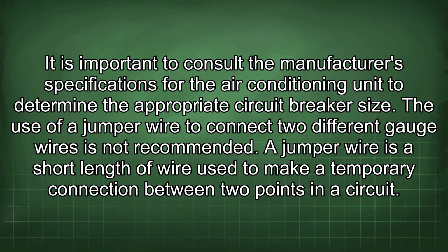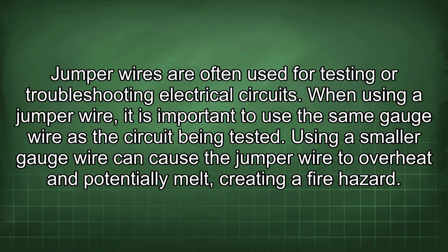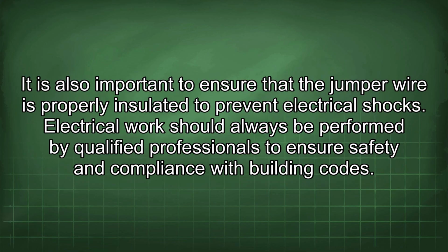The use of a jumper wire to connect two different gauge wires is not recommended. A jumper wire is a short length of wire used to make a temporary connection between two points in a circuit. Jumper wires are often used for testing or troubleshooting electrical circuits. When using a jumper wire, it is important to use the same gauge wire as the circuit being tested. Using a smaller gauge wire can cause the jumper wire to overheat and potentially melt, creating a fire hazard. It is also important to ensure that the jumper wire is properly insulated to prevent electrical shocks.